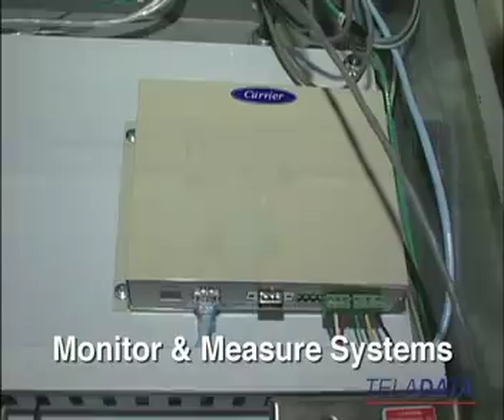Imagine having to build a data center in a high-rise under traditional floor space. Well, Adobe's Dave Morrison had to meet that challenge. We're standing in a space that used to be an aisleway with conventional offices. Installed two separate air conditioning systems in here. The first is conventional CRAC units that feed overhead ducting that's on the other side of the server cabinets here. And the second is XDC systems, and you can see one of the XDC chillers right here. And this feeds refrigerant to these overhead XD units.